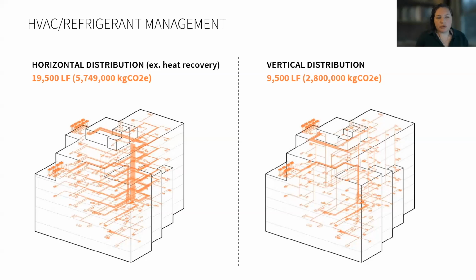So we want to reduce the risk of leaks as much as possible. We believe we can achieve the same level of comfort without heat recovery and significantly lower the amount of refrigerant lines, which of course keeps costs down too. Refrigerant can leak at fitted connections, which are all built on site, so brazed and flared copper connections. It's important to follow through with quality control procedures to construct and then charge these lines.